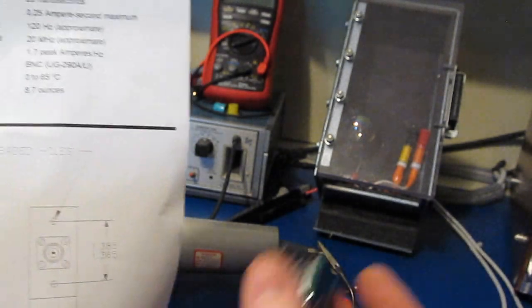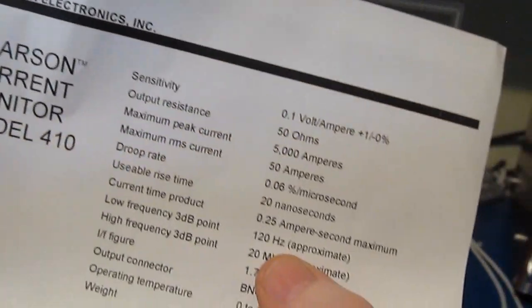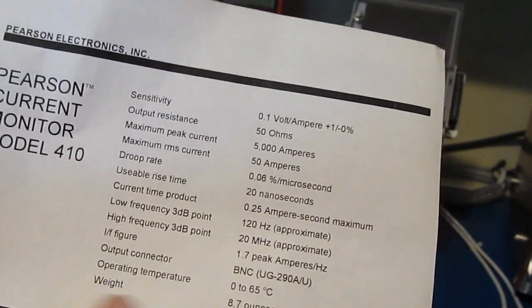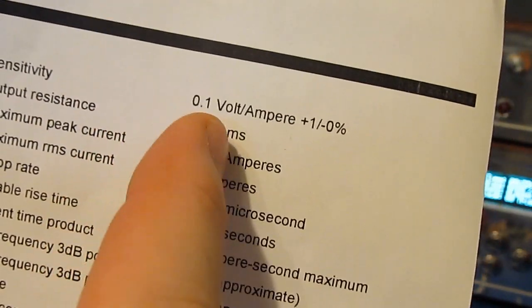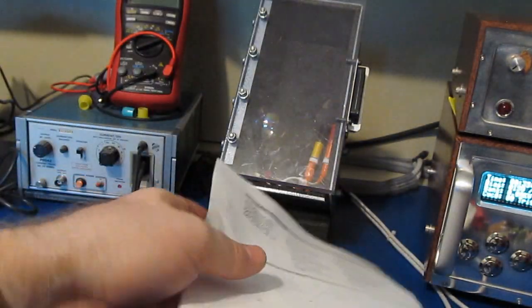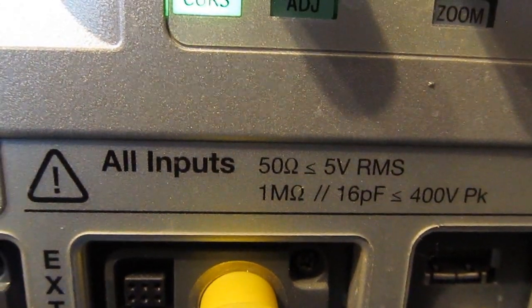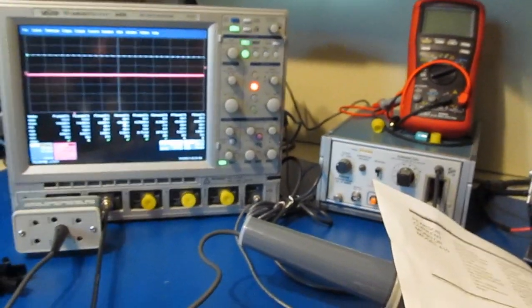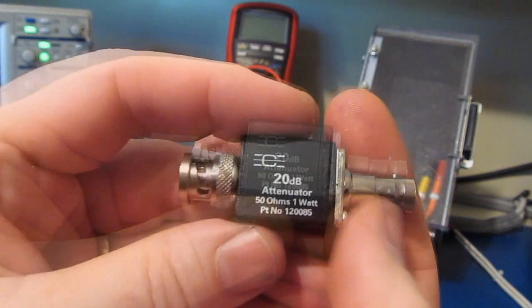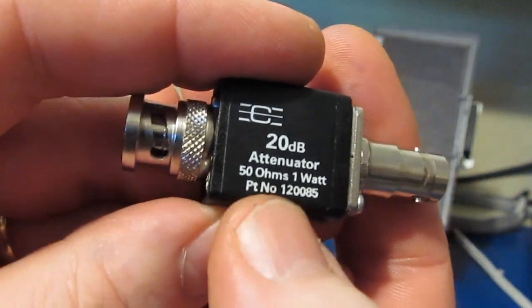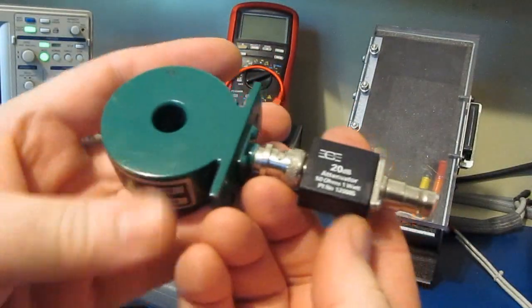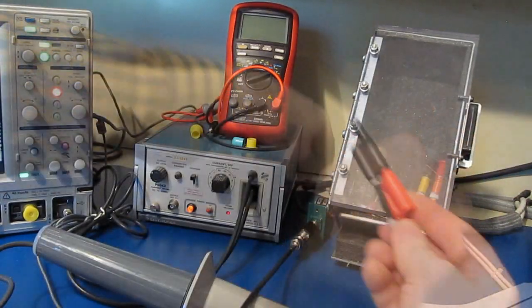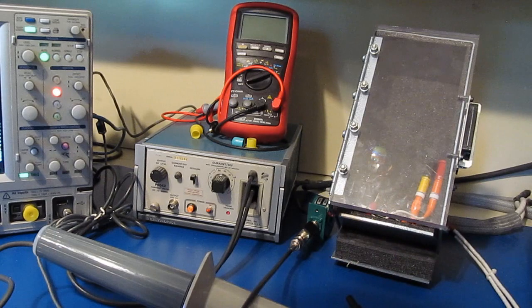This is looking at the datasheet for this particular model. Sensitivity is 0.1 volts per amp, meant to drive into a 50 ohm load. It can handle a peak current of 5,000 amps. The low frequency 3 dB point, of course it's a current transformer so it can't measure DC, is approximately 120 hertz. That's going to be fine. And the high frequency 3 dB point is 20 megahertz. We're expecting a peak current of roughly 500 amps. At 0.1 volts per amp, we're talking about 50 volts peak. Our oscilloscope with a 50 ohm selection is rated for 5 volts RMS. So putting 50 volts into that oscilloscope probably isn't going to be too healthy for it. So what we're going to be doing is using an attenuator, this one is 20 dB. That's going to reduce our voltage by a factor of 10x.